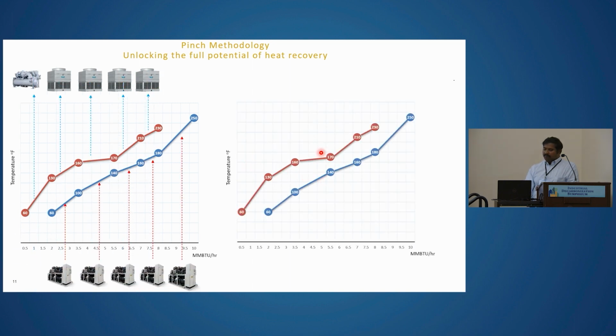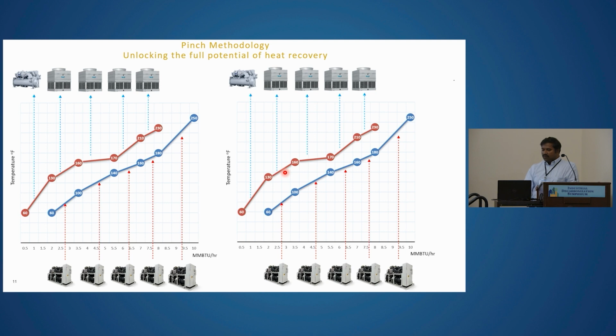This is what we call the pinch temperature or pinch point, where the source comes close to a sink, and beyond this point and below this point, we can do direct heat recovery. So for example, currently this particular process cooling is done with the help of a cooling tower. This process heating is done with the help of a heat pump. Instead of doing this, we can do direct heat recovery: take this 230 degree Fahrenheit process liquid and heat up another process from 160 to 180 degrees Fahrenheit with the help of a shell and tube heat exchanger or a plate heat exchanger. You don't need electricity to do this particular heat transfer, just a direct heat transfer.